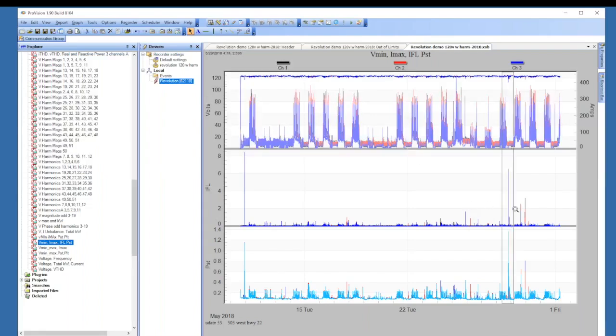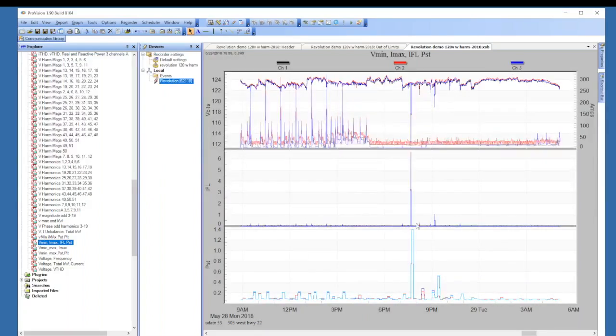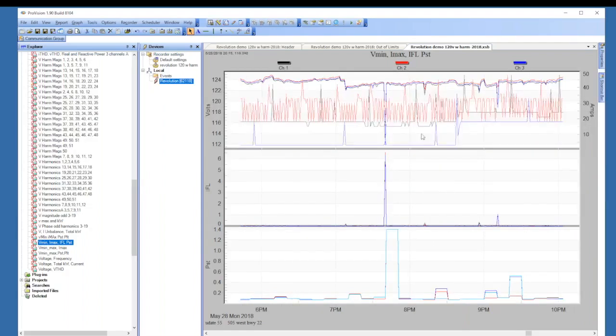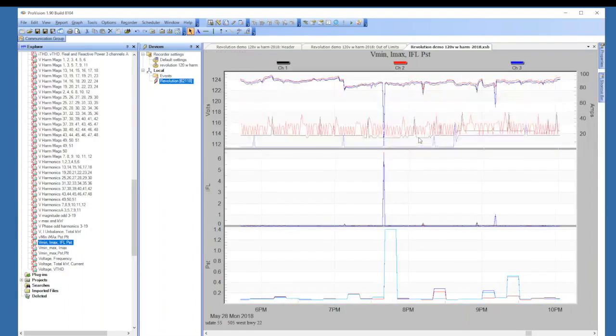And basically what you're doing is you're looking at your spikes on the IFL, and you can see that they correspond more with the drop down of current. So we don't have any inrush there, but we do have a voltage drop. So therefore it's not the load that caused this spike in the IFL. So something happened on that line further up. So if you really did have a lot of IFL in there, that's how you can figure out whether or not it's the load that's causing it.